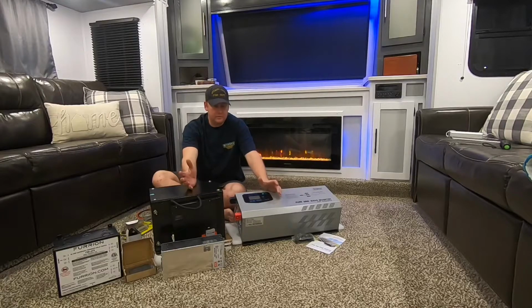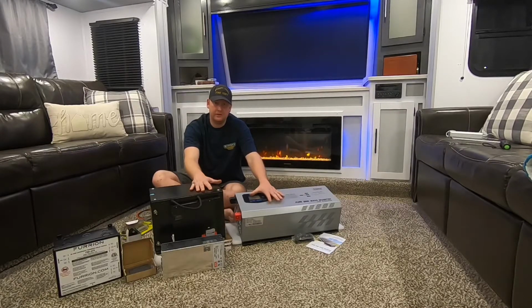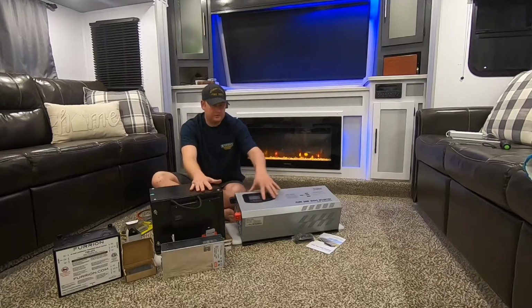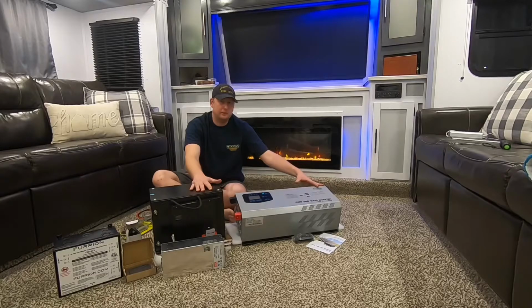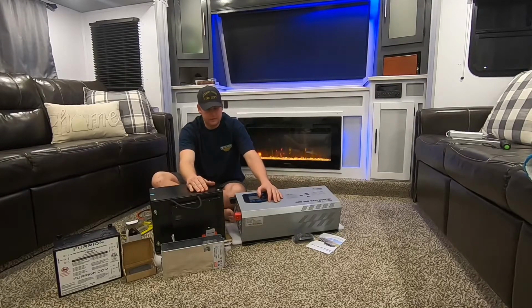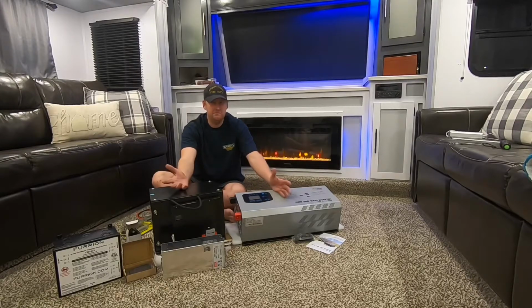When I did the math on what I was trying to do, each pole would never really exceed the 25 amps that each leg puts out. It's important to remember it's a 50 amp, 6,000 watt inverter, but each pole only puts out 3,000 watts together. Running my AC, I'm not going to run the air conditioner and the heater at the same time, it just doesn't make sense.